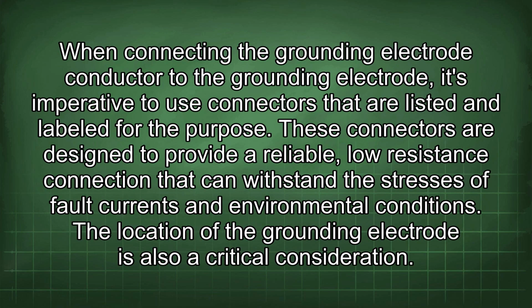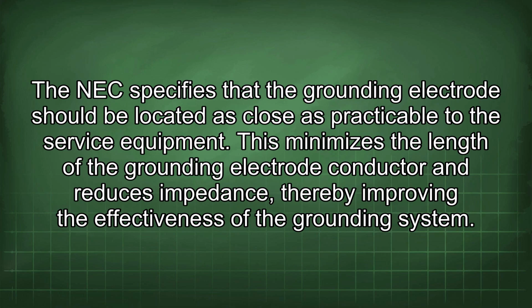When connecting the grounding electrode conductor to the grounding electrode, it's imperative to use connectors that are listed and labeled for the purpose. These connectors are designed to provide a reliable, low-resistance connection that can withstand the stresses of fault currents and environmental conditions. The location of the grounding electrode is also a critical consideration. The NEC specifies that the grounding electrode should be located as close as practicable to the service equipment. This minimizes the length of the grounding electrode conductor and reduces impedance, thereby improving the effectiveness of the grounding system.